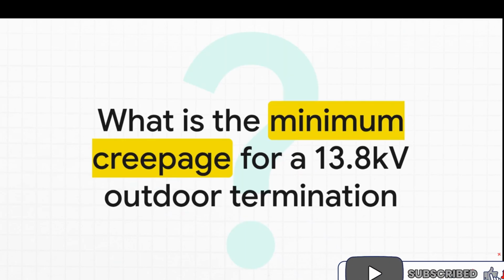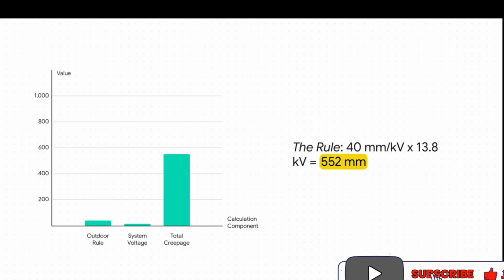Okay, here's another classic. This one's a numbers question. It's designed to see if you know the really specific rules for high-voltage terminations. So, what's the magic number you need to remember here? And the answer is actually really simple if you just know the rule. For any outdoor termination, the standard demands 40 millimeters of creepage distance for every kilovolt of power. So you just take 40, multiply it by the system voltage, 13.8 kilovolts, and boom, you get 552 millimeters. It's easy points in an interview if you're ready for it.